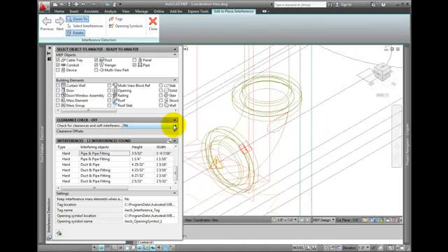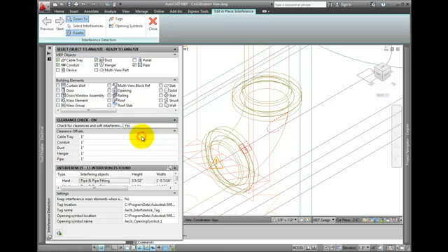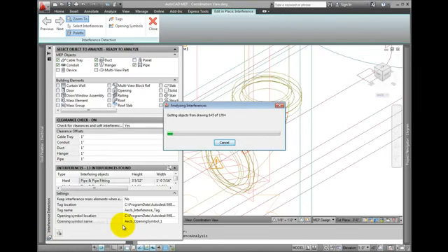Go back and select Yes for clearance checks. Set each item to 1 inch. When finished, start the analysis again. In this project, this can take anywhere from a few seconds to a couple of minutes. But clearances can add to that time substantially. So I usually run a hard detection first, fix the errors, and then use clearances once I've worked out most of the hard clashes.